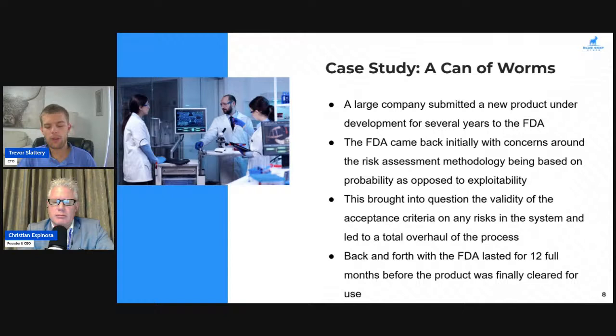The device manufacturer comes to us, asks for our assistance to start fitting it to exploitability and work with the FDA's deficiencies. But as we do that, the FDA starts pulling onto this thread, and they're saying, well, now that we're looking a little bit deeper into this, you're missing these controls. This implementation is insecure. We don't like how you're integrating into existing environments. And it ended up leading to some significant design overhauls of the medical device. We had to go through full new rounds of testing since previous testing was deemed out of date. It became a whole long process with 12 full months of FDA interactive review before we finally got this product cleared for market, all because the FDA identified one deficiency that they started to look into a little bit more and start pulling on that thread.